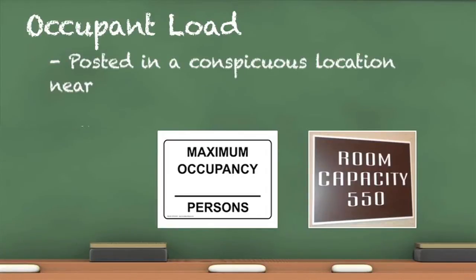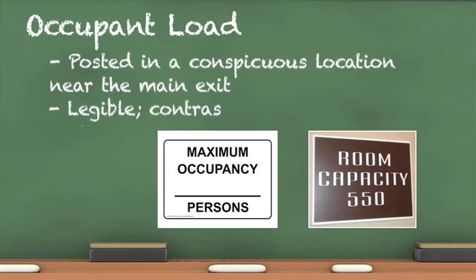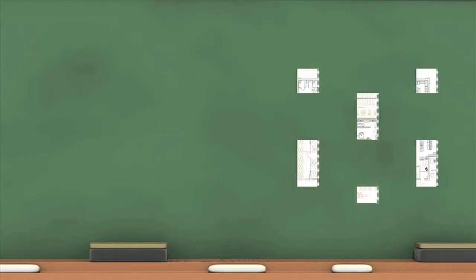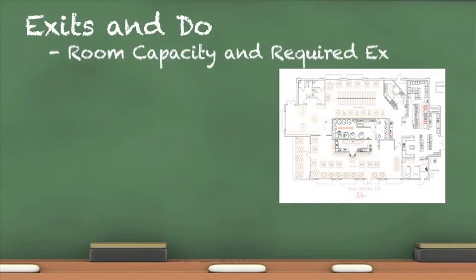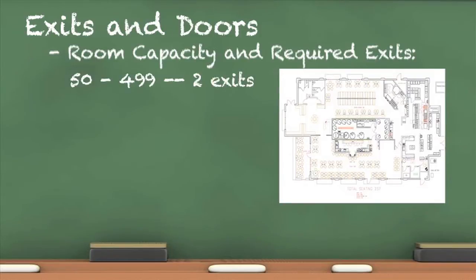Every room or space in an assembly occupancy shall have the occupant load posted in a conspicuous place near the main exit. The signs must be legible with contrasting text and background. There are many factors that determine the number of required exits — this is just a guideline: 50 to 499 people requires 2 exits; 500 to 999 requires 3 exits; 1,000 or more requires 4 exits minimum.